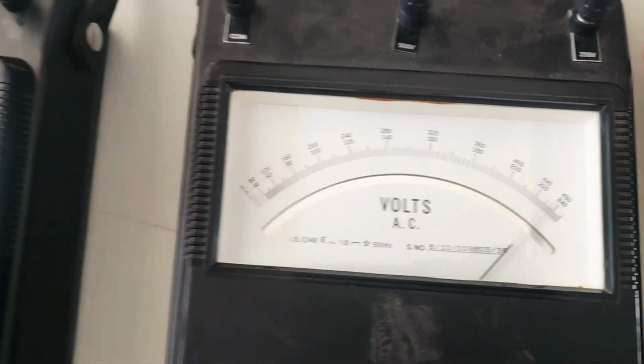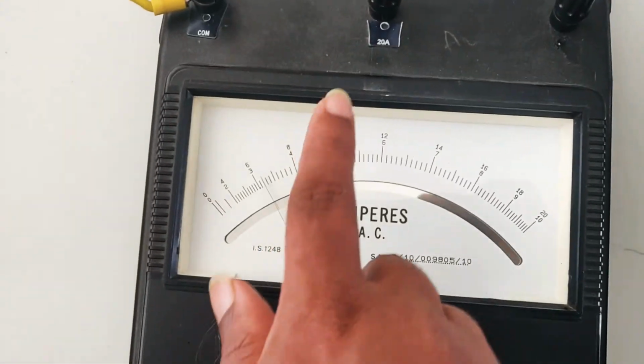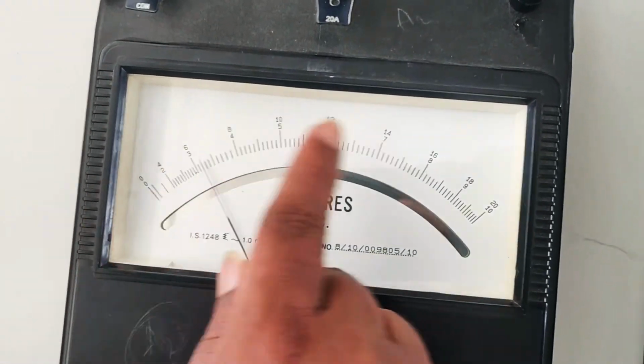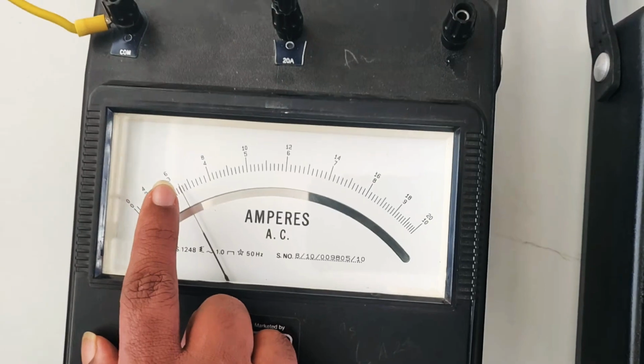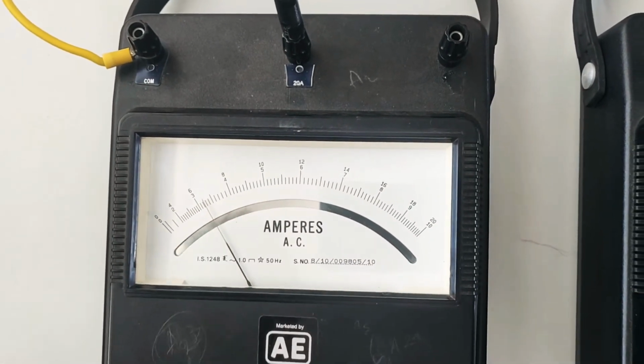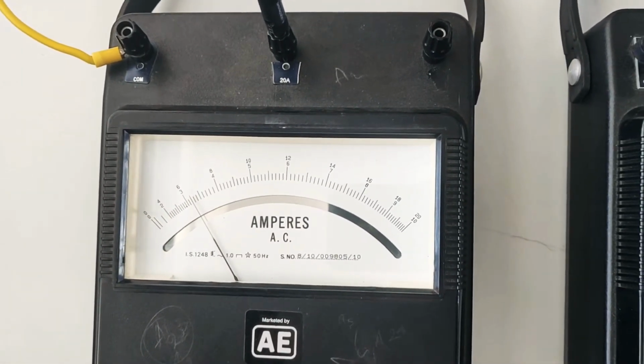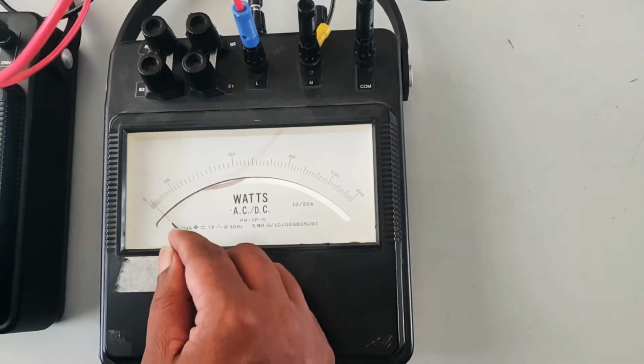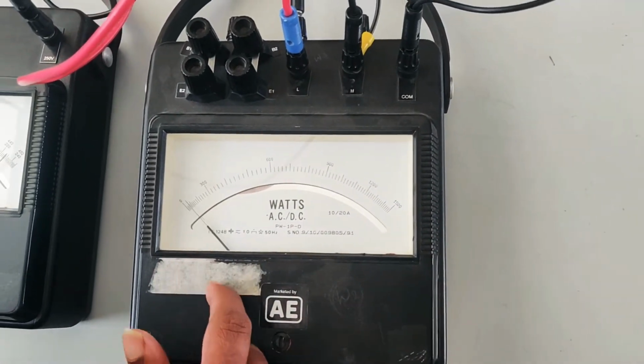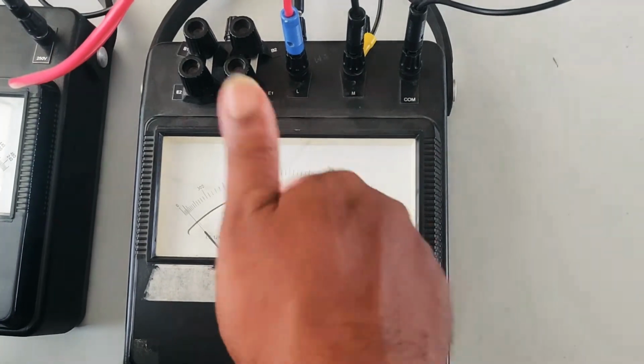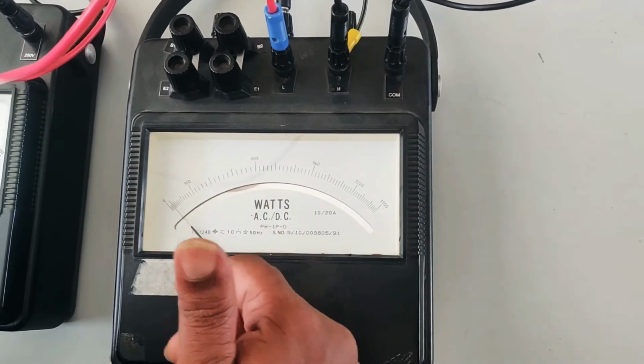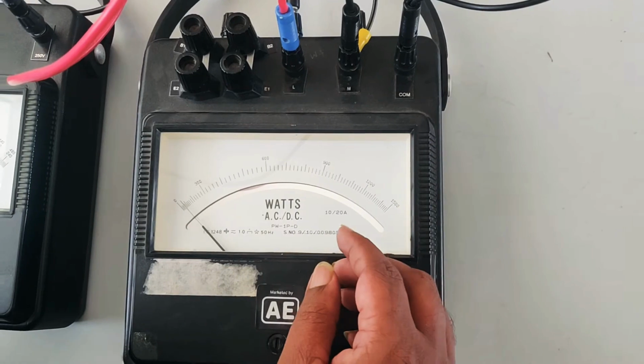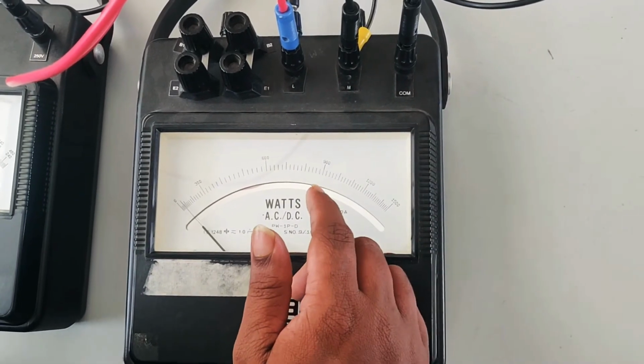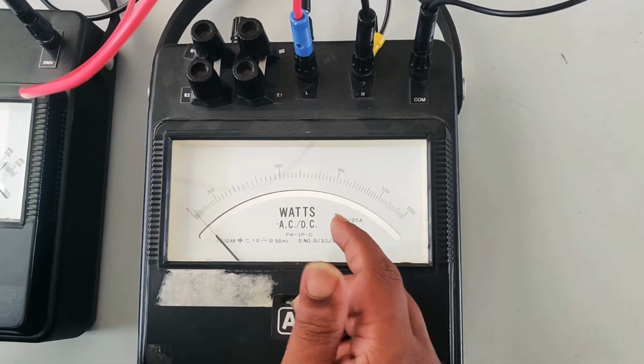Okay, and you can observe the no load current, on the 10-20 amps range, on the upper scale. 6.6 will be the no load current. And then the wattage is 80 watts. That is, you have to multiply with the wattmeter constant also. 80 multiplied by the wattmeter constant is nothing but VI cos phi divided by FSR.